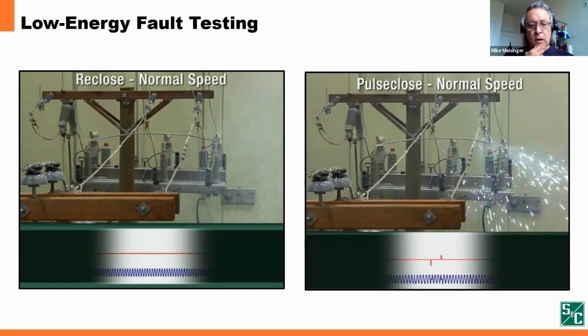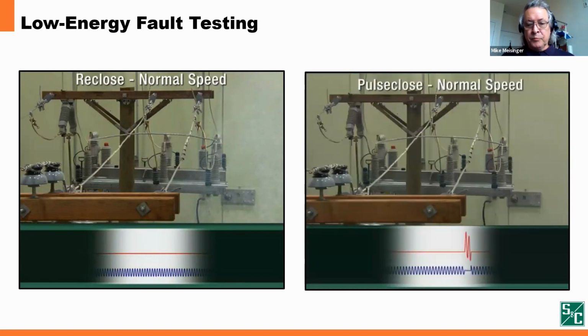In contrast, we're going to show you now what low energy fault testing looks like, and we're going to essentially respond quickly to this fault and then apply low energy tests. You're going to see two spits, because once we identify a potential fault, we retest again using an opposite voltage polarity. So go ahead and run that video, please, Kleber. Test 1, 2 spits. Test 2, 2 spits. Test 3 coming up. Dramatically different approaches to determining whether that fault is still present or not. And you don't see any significant conductor movement except that from the initial fault.